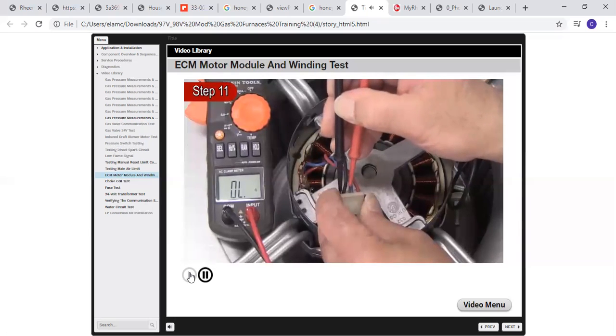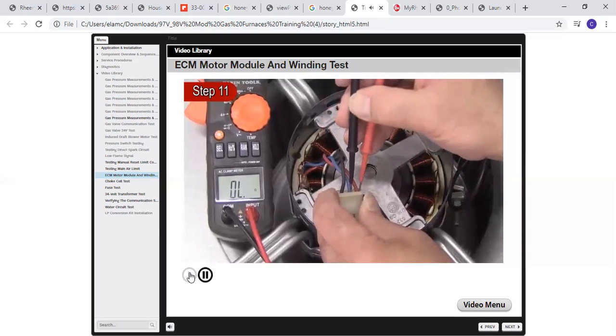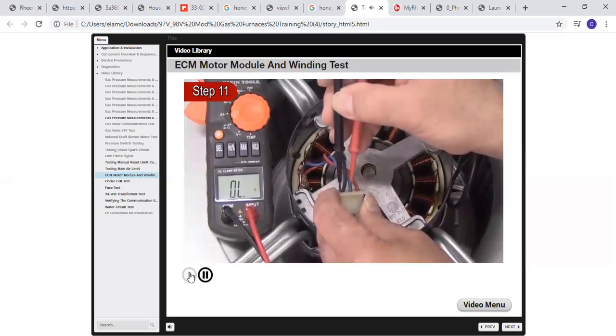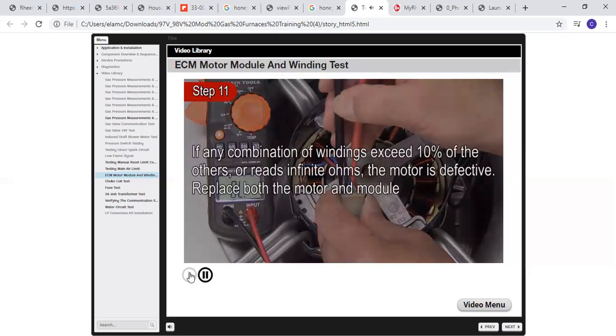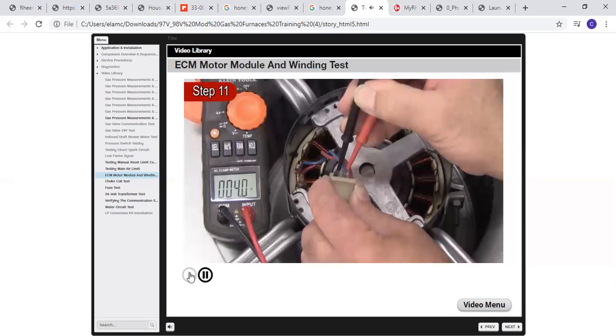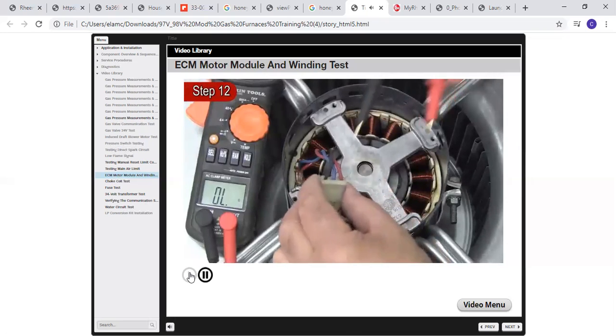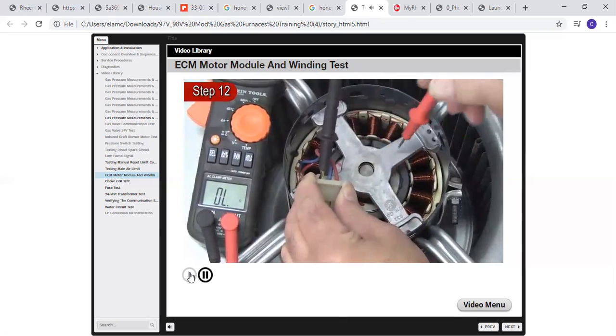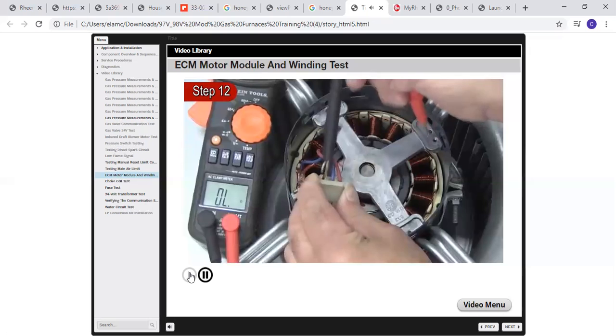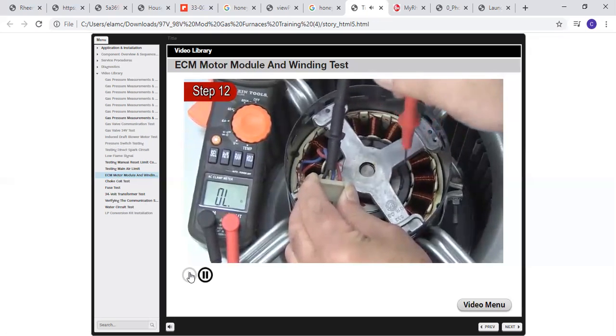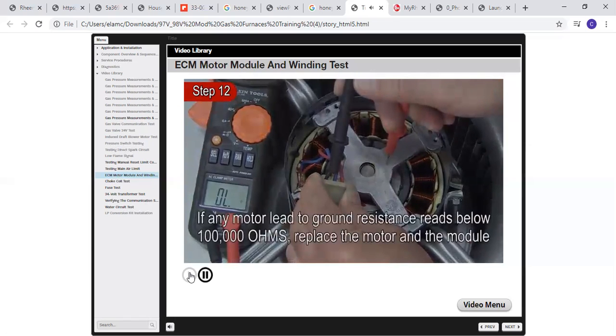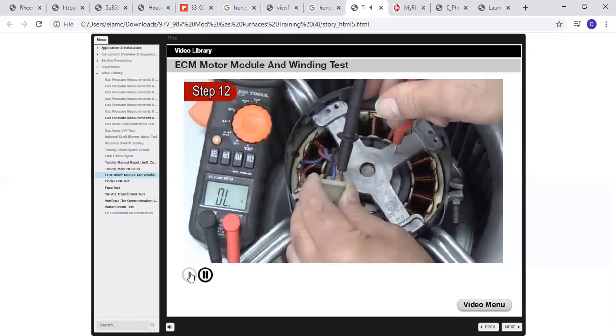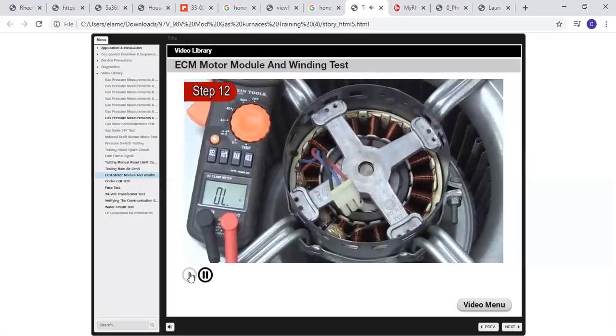If the windings are all infinite ohms, allow time for the internal overload of the motor to cool. Recheck the ohms after the motor has cooled. If any combination of windings exceeds 10% of the others or reads infinite ohms, the motor is defective. Replace both the motor and module. If the motor checks out okay, continue to the next step. Step 12. Measure for electrical resistance between each motor lead and the end plate of the motor. There should be infinite ohms between each motor lead and the chassis of the motor. If any motor lead to ground resistance reads below 100,000 ohms, replace the motor and the module. If the motor windings check out okay, go on to the next step.